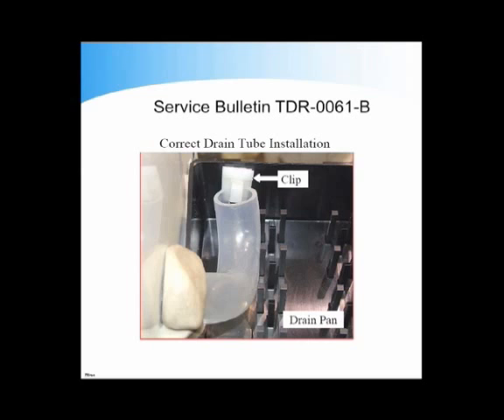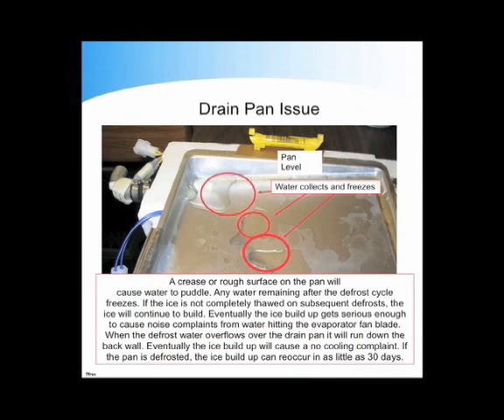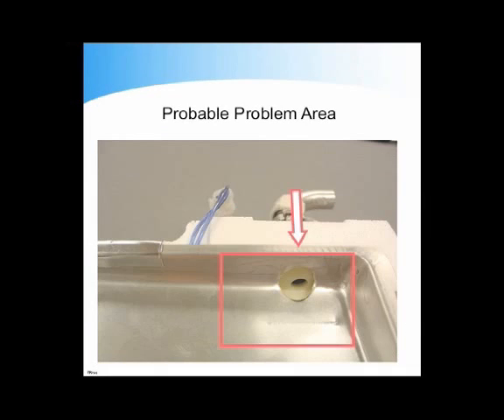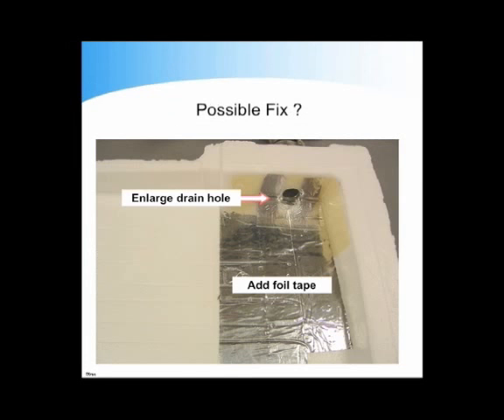Eventually, the ice buildup gets serious enough to cause noise complaints from water hitting the evaporator fan blade. When the defrost water overflows the drain pan, it will run down the back wall. Eventually, the ice buildup will cause a no cooling complaint. If the pan is defrosted, the ice buildup can reoccur in as little as 30 days. Probable problem area: a kit is currently on test to add additional heat to the drain area. Possible fix? The kit will have a larger drain hole and foil tape added to the drain area. Additional tape is added to the top side of the drain pan.